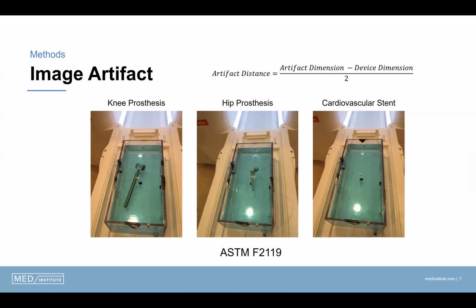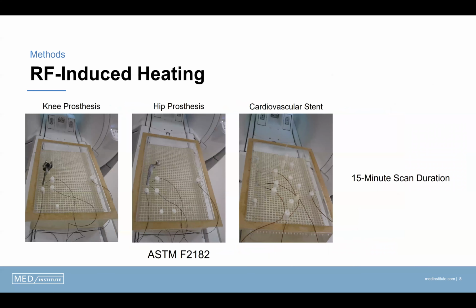Image artifact testing was performed according to ASTM F2119 for each of the devices at each of the field strengths. Gradient echo and spin echo scan sequences were conducted with a 10 millimeter slice thickness. Images were evaluated for the worst case artifact distance, which was calculated as shown on the slide. RF-induced heating of each device was evaluated according to the ASTM F2182 standard. The devices were submerged in a gel phantom with temperature probes positioned as shown in these images. Temperature rise after 15 minutes of scanning was compared for each device at the various field strengths.